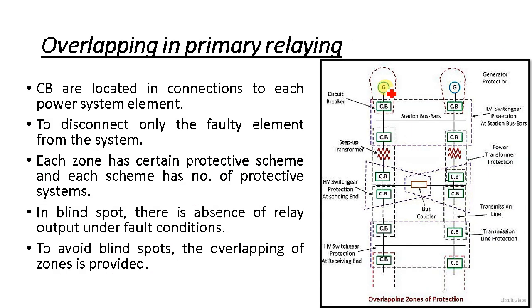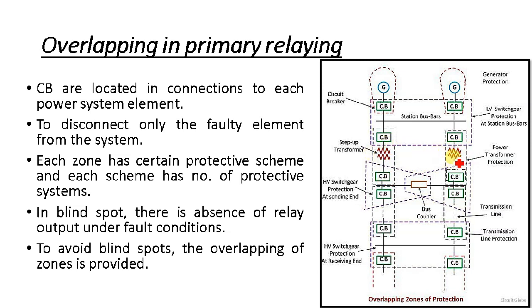Now let us discuss overlapping in primary relaying. Here you can see the same diagram but we are dealing with LV switch gear protection at the bus bar, the step-up transformer at the LV side, switch gear and protection at the sending end, and HV switch gear and protection at the receiving end. Circuit breakers are located in the connection to each system element. At each end of the bus bar and transformer, there is a circuit breaker so that any element of the power system can be disconnected.